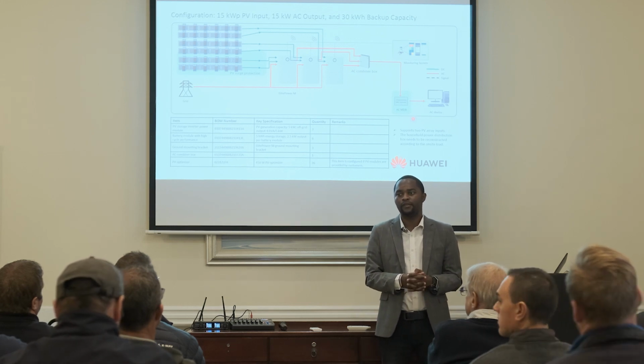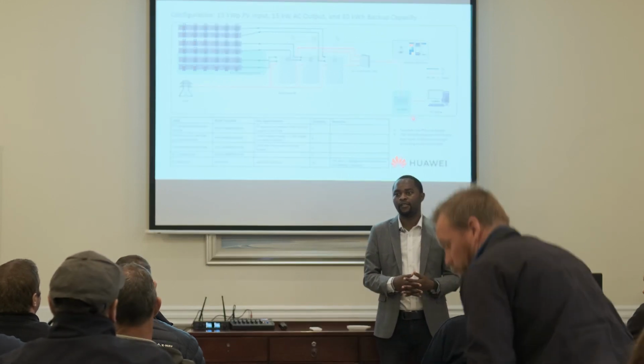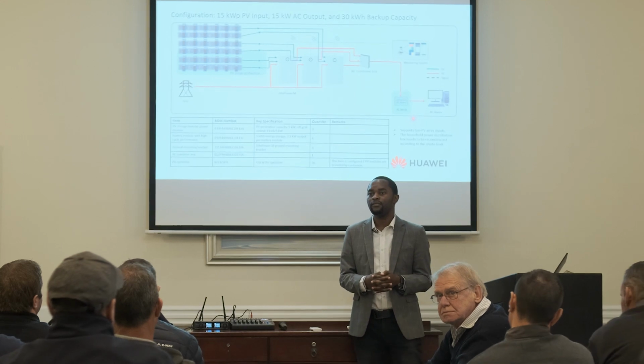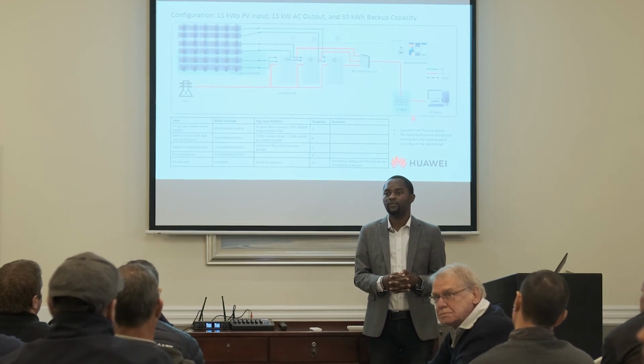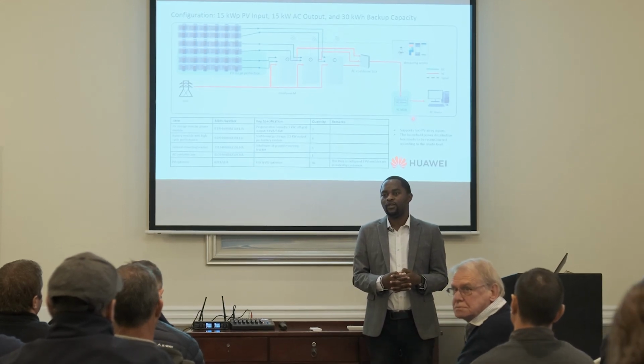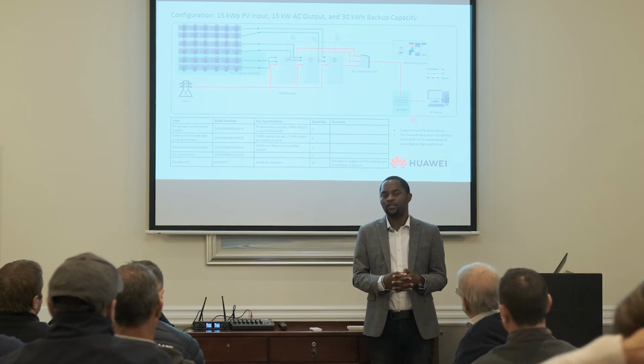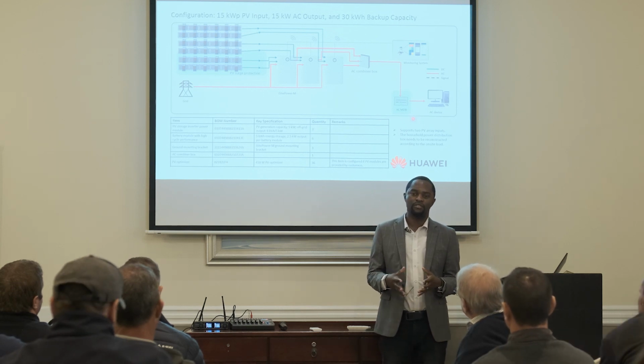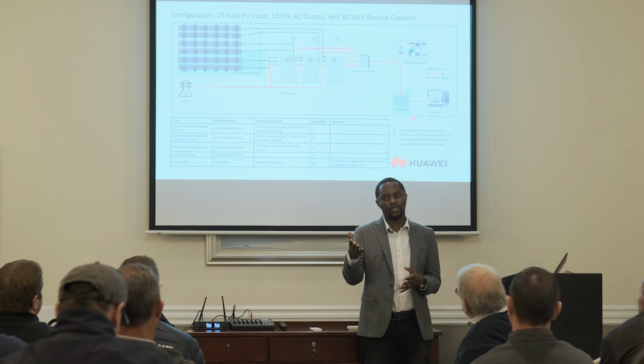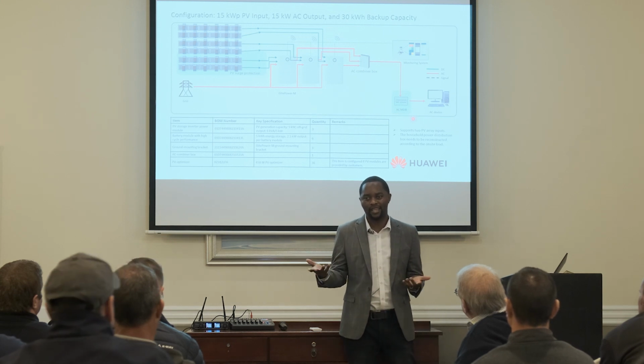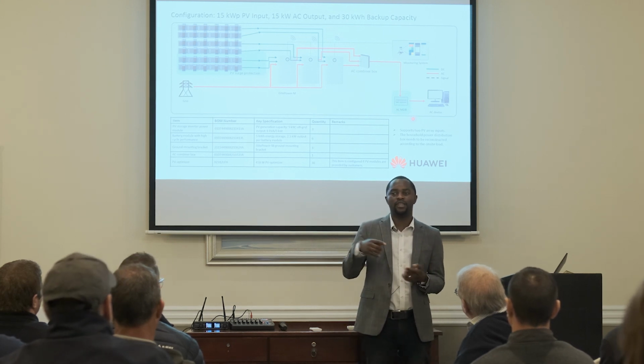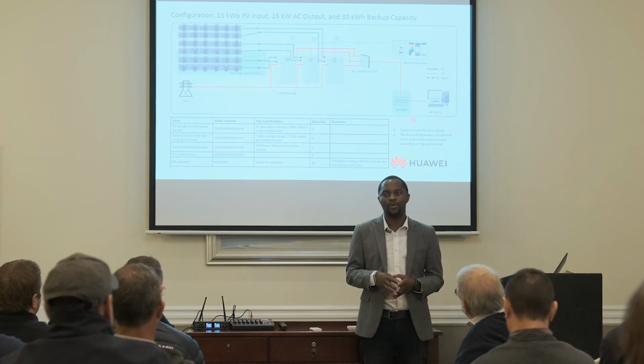Just on the generator, it's not like your other inverters that have to have an AVR because of your range and your AC. So does it have to be a stable input from a generator, or can it be, like, a petrol generator that fluctuates? Yes, so the challenge that we've been having with the generator, especially the smaller petrol generator, 6 kVA, is that the frequency is not stable and the voltage is not stable. It jumps up and down.